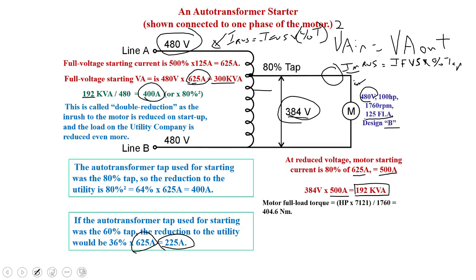So for example here, on our motor, we've got a 100 horsepower motor and its full load RPM is 1,760. Well, we can calculate its normal running torque, its full load torque. Take our horsepower, times it by 7121, divided by 1,760. So this at full load produces 404.6. So torque full load equals 404.6 Newton meters.